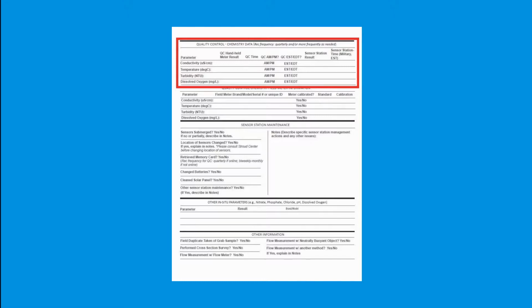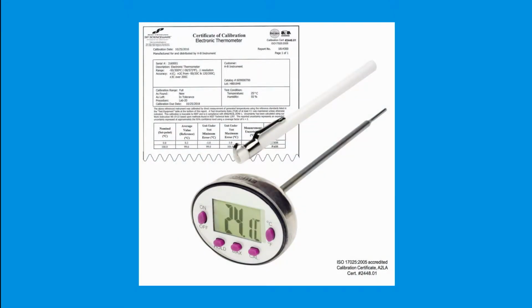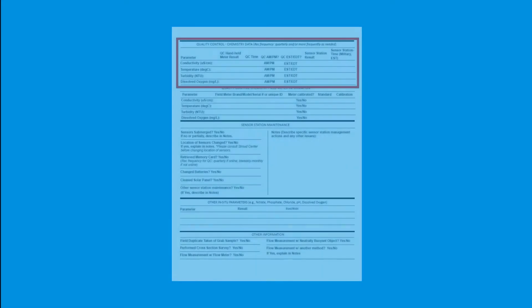Below conductivity is water temperature. Remove the protective white sleeve from the calibrated thermometer. Turn the instrument on via a button. Lower the metal probe into the water and wait for the value on the screen to stabilize. You can press the hold function to keep the stabilized value on the screen even if you move the instrument around or take it out of the water. Be sure to record the time when the value was stabilized.